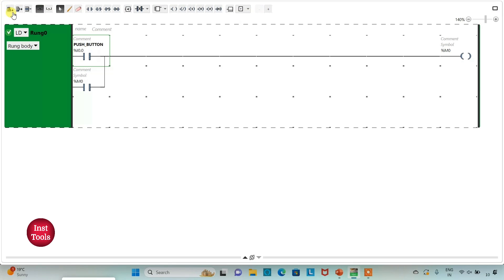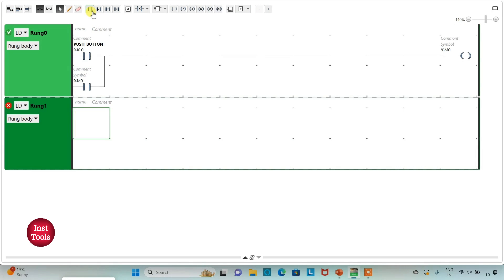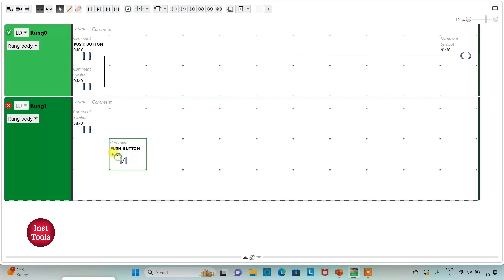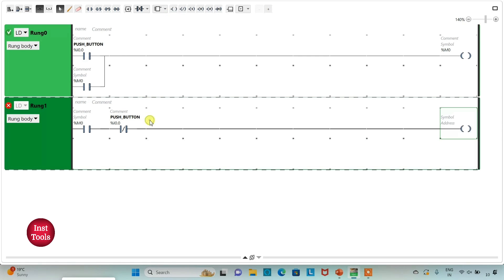Then I will add a new rung. I will insert a normally open contact and assign address M0 to it. Then I will insert a normally closed contact and assign address I0.0 to it, which is the push button. Then I will insert a coil and assign address M1 to it, which is another memory bit. So when M0 is true and the push button is released (I0.0 is off), then M1 will be true.